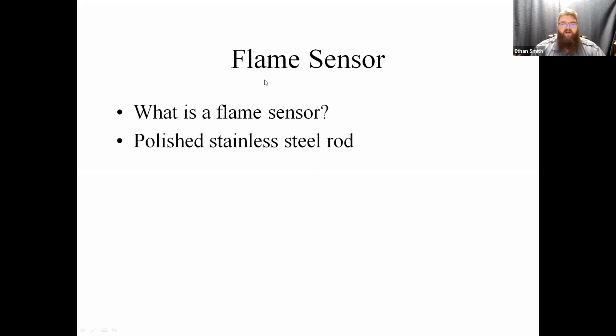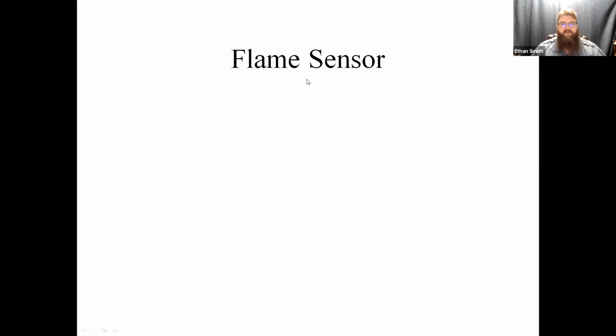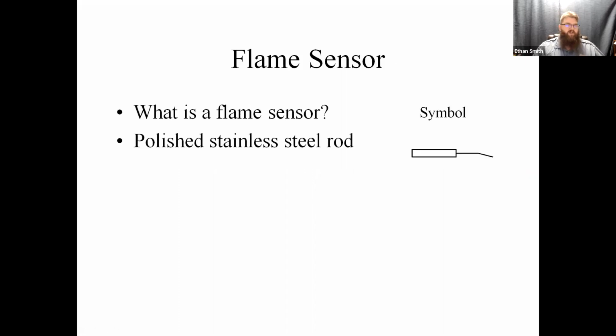Okay. So in order to get a flame sensor to work again, all we have to do is clean it. Okay. And because it's a polished rod, we want to just take the crap off of it without taking the polish off of that rod. If we use a file or something like that to clean that flame sensor, all we're doing is adding surface area. We're putting big grooves in that flame sensor, adds surface area to that flame sensor, which on the surface may seem like a good thing, but what it really does is it makes it more prone to fouling.